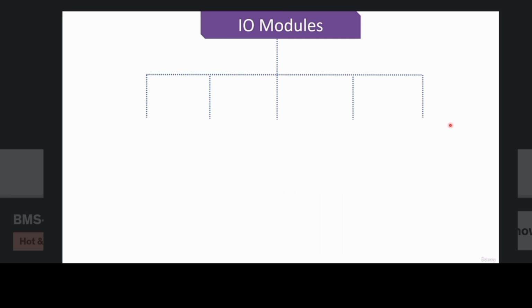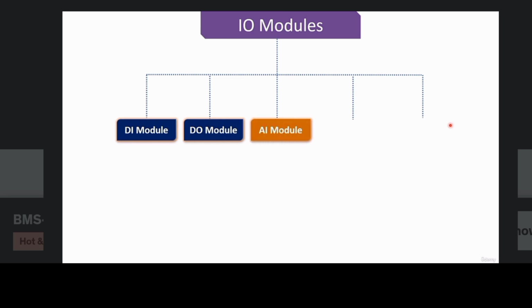There are different types of expansion I/O modules, which are DI modules. DI means digital input modules. Then we have DO or digital output modules, analog input modules, analog output modules, and then there can also be mixed I/O modules. In mixed I/O modules, all different types of I/Os are mixed together. Every manufacturer has different types of I/O modules with different model numbers and characteristics. Every manufacturer has their own I/O modules with different part numbers. We will go through panel bus I/O modules which are used by Honeywell. We will go through the manual of these I/O modules to see the details about them.